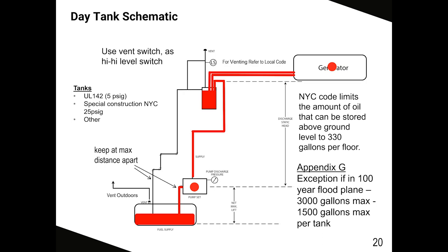So John, as you can see with the venting issue here, it's pretty difficult to use a UL-142 tank inside a building in New York City, isn't it? It is very difficult. You have to meet your code requirements, and really the best application I feel for those types of tanks is outdoors or at grade, someplace where you are able to control the height of the vent line.